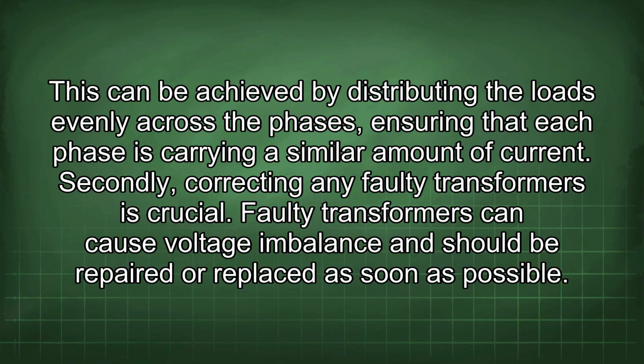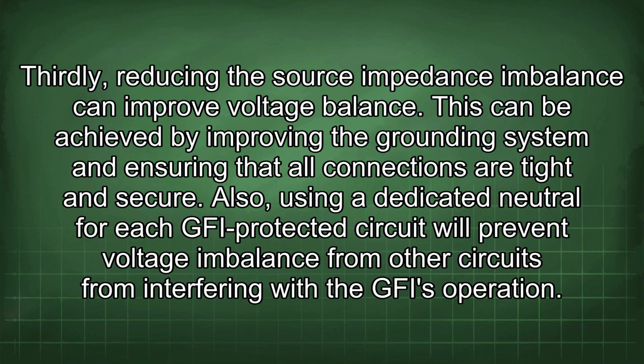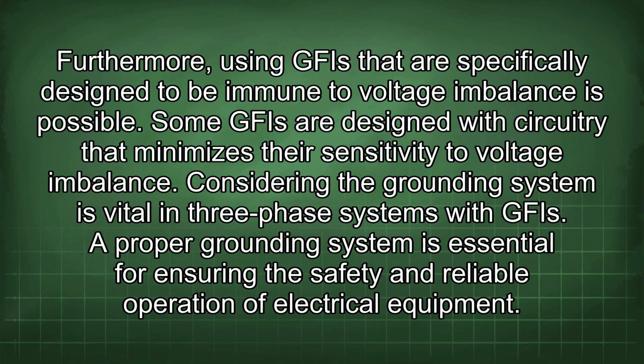Faulty transformers can cause voltage imbalance and should be repaired or replaced as soon as possible. Thirdly, reducing the source impedance imbalance can improve voltage balance. This can be achieved by improving the grounding system and ensuring that all connections are tight and secure. Also, using a dedicated neutral for each GFI protected circuit will prevent voltage imbalance from other circuits from interfering with the GFI operation. Furthermore, using GFI that are specifically designed to be immune to voltage imbalance is possible. Some GFI are designed with circuitry that minimizes their sensitivity to voltage imbalance.